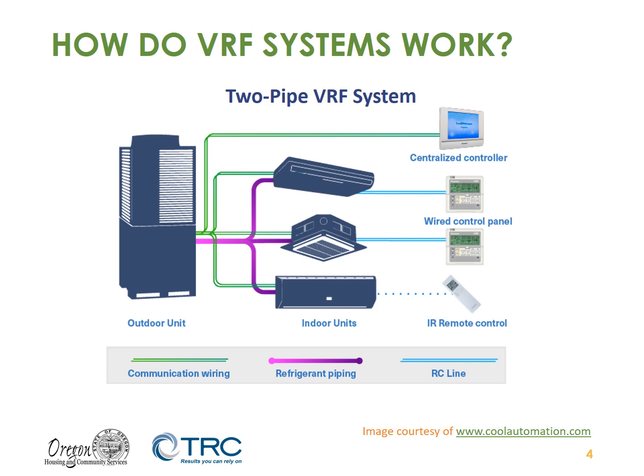Within these VRF systems, we have both two-pipe and three-pipe models. Let's start first with a two-pipe model. This is most similar to the traditional mini-split or multi-split system that we're familiar with. I mentioned this earlier in the previous image, where we have our refrigerant piping that comes in a high pressure gas and low pressure gas side of the equation, and it comes out of the outdoor unit and independently goes to each of the indoor units. These systems can be controlled individually in each zone. So in the diagram that you see here, you see some wired control panels and an infrared remote control. Each one of them can be controlled individually, which would probably be our preference in a multifamily scenario.